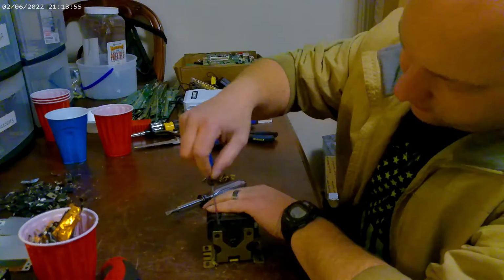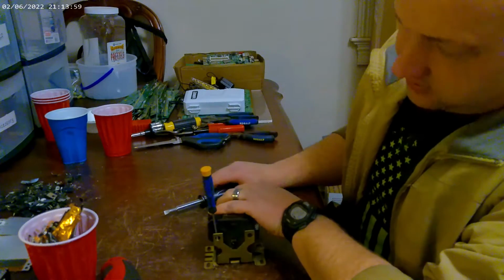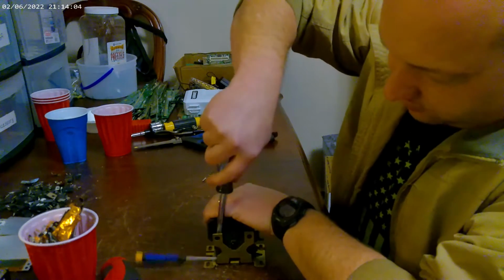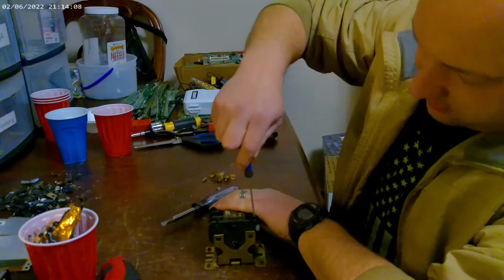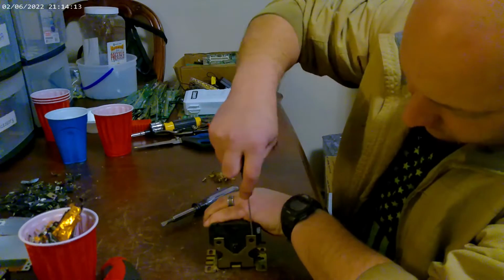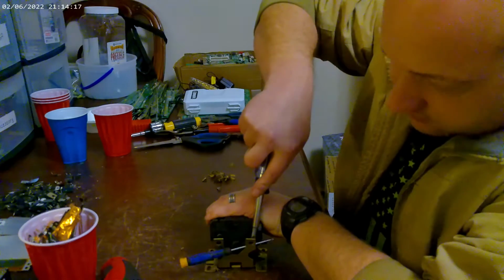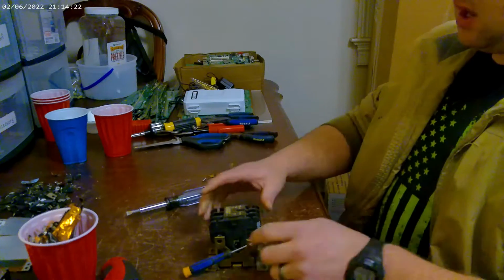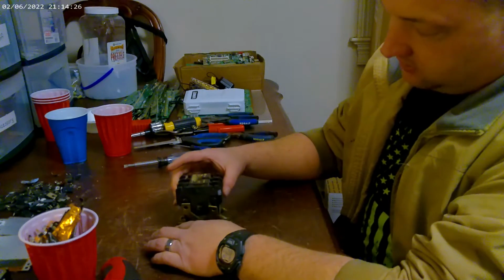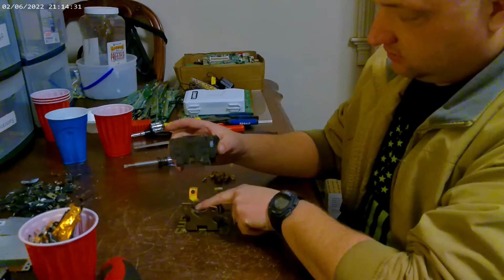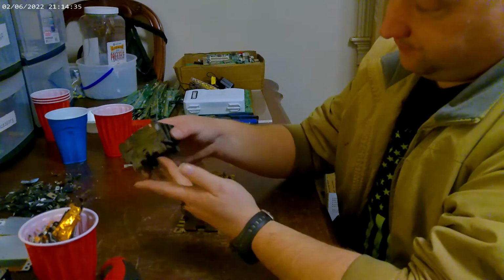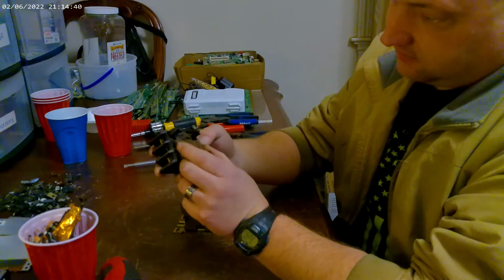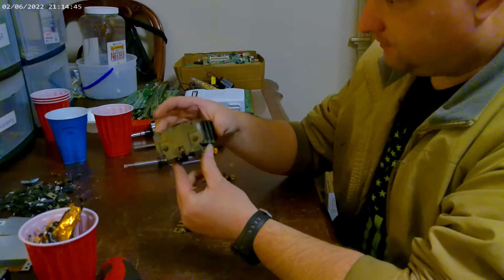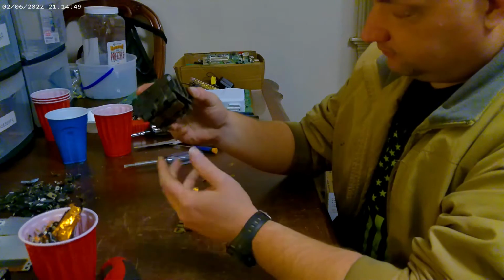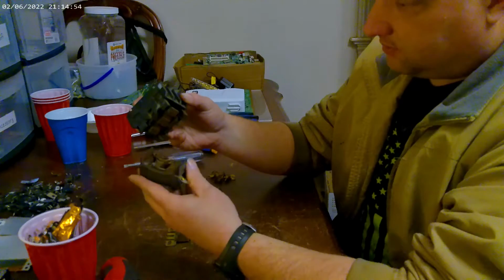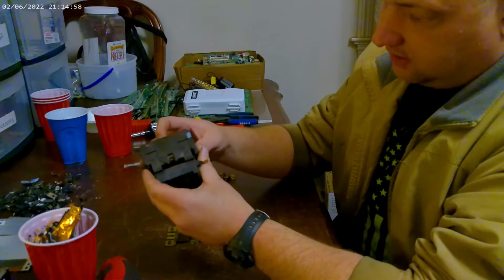So on that side, basically, I just took the small flat screwdriver, pushed it in like that, just to make a spot. Put the big screwdriver in and pried it back so it doesn't fall back into the lock position. So it's ready to fall out, but I'm just trying to show y'all so you can see. You're going to take this contactor and then lift it up. So, spring loaded. That's what keeps it held up when it's not engaged. Here's your actual contacts that close everything. When this coil on the bottom here becomes magnetized, that pulls that contactor down to make contact.